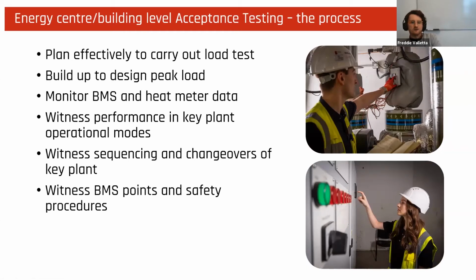So yeah, load testing is able to prove this operation for both phased and whole developments. Once all the plant room equipment is commissioned separately and a sufficient number of endpoints are connected to the network and commissioned correctly as well, the load test can be undertaken. We'd recommend that this is carried out with the BMS engineers and also boiler or heat pump manufacturers on site to ensure that any adjustments can be made there and then based on the performance observed.